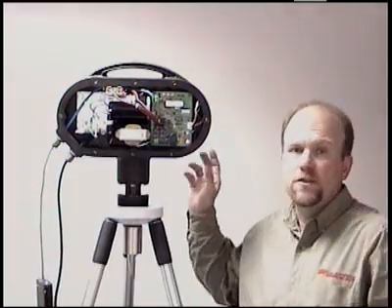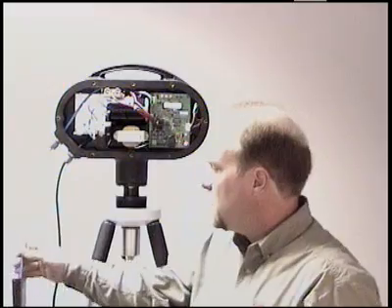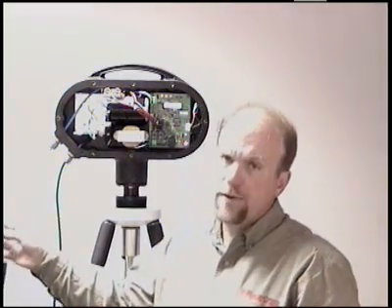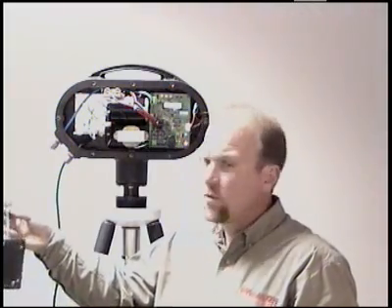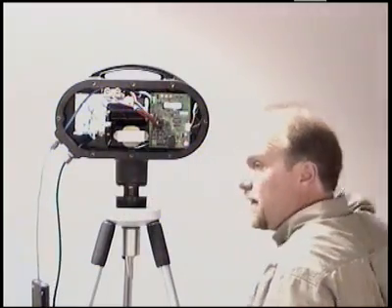Electronic features. We operate on an RS-485 network, meaning that from our control source we run a twisted pair shielded communication line in series to each remote. So one cable will go up to the first remote, back out and daisy chain on.